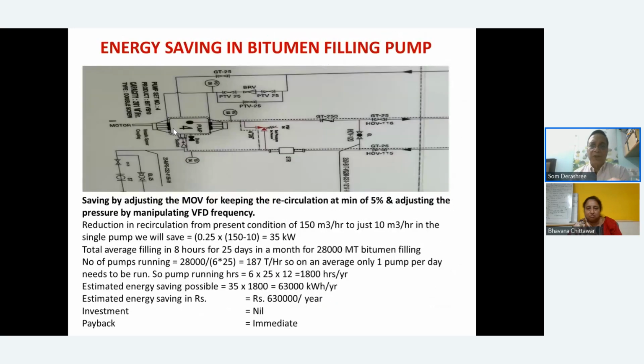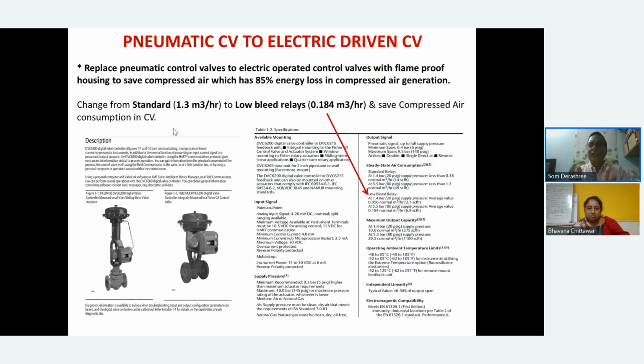There were a lot of pneumatic valves. All these valves were pneumatic valves actually, whatever they had. So we said change over from pneumatic; they have only 8 pneumatic valves. For that they had a compressor, and with an air compressor, you know, 85% of the energy is already lost as heat. There are now electrically operated MOVs available, and though they don't need a fireproof area, they still insisted no, sometimes solvents come and all that.